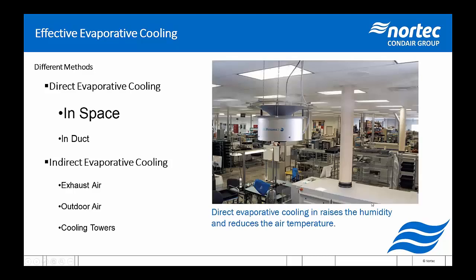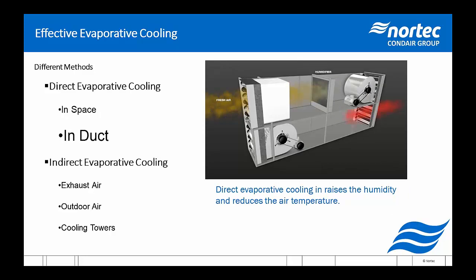So in space, this is exactly as it sounds: direct evaporative cooling in space. In this situation, we have a high pressure system spraying water directly into the room. And inside this room, we're using the room temperature to reduce the air temperature. In the duct, it was fairly straightforward. This would be a classic humidification where we're putting in fresh air, preheating or pre-cooling, and running it through the evaporative humidifier to cool further. So typically, if you needed a heating coil, and a cooling coil would come after the humidifier. Generally, the goal in this situation would be to reduce the overall cooling needed, not to reduce peak load or anything like that.